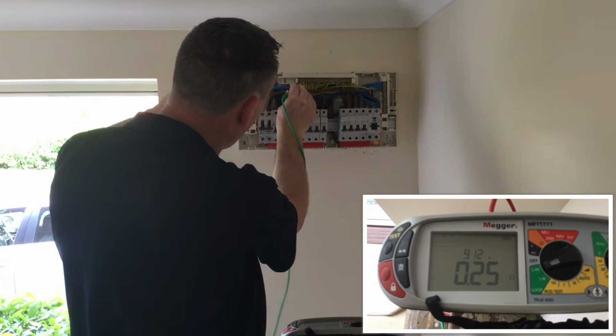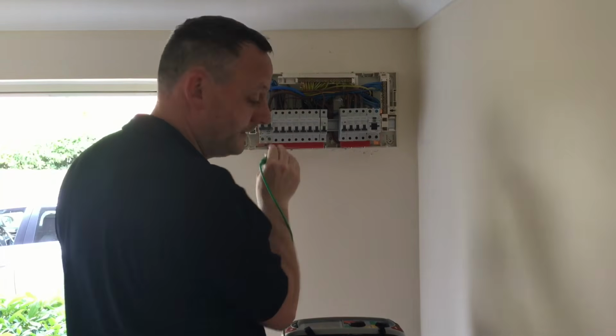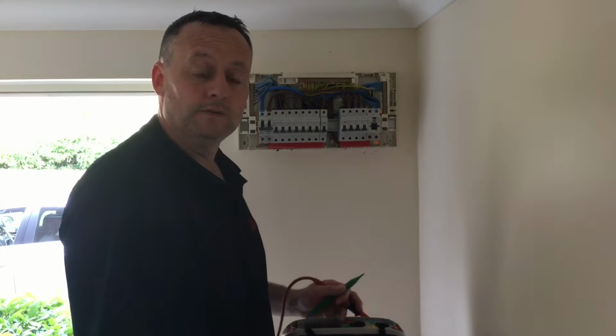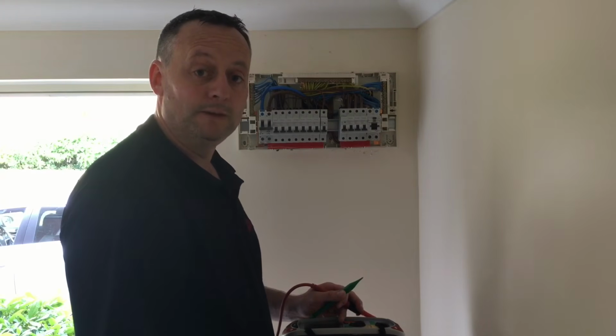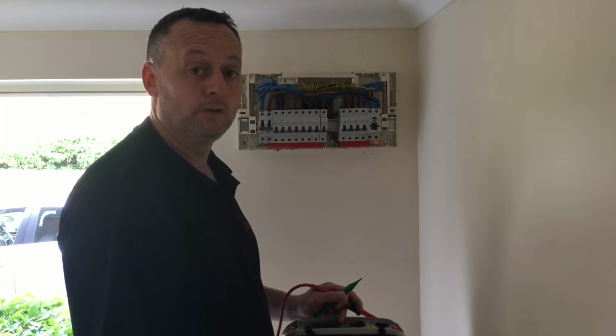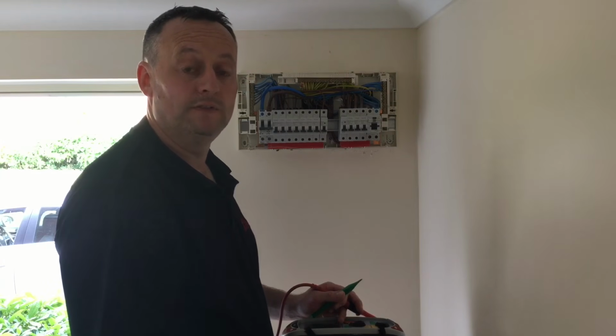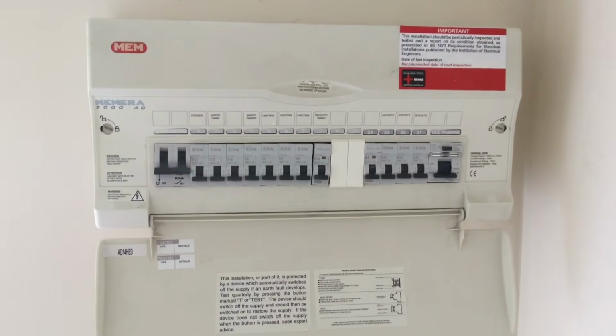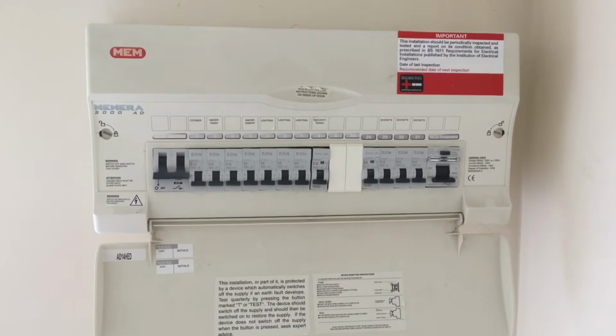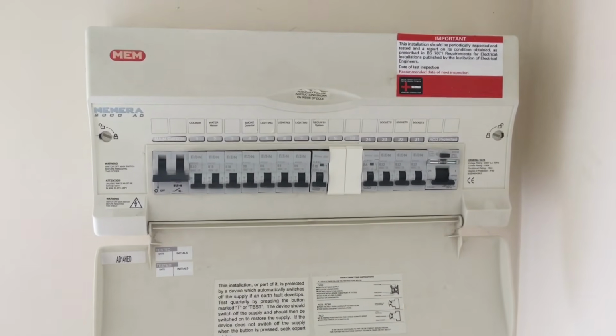I'm going to pull off the line conductor and I'm going to pull off the earthing conductor. There we go. The external earth fault loop impedance has been measured. It's less than the 0.35 ohm maximum, being 0.25. Therefore, we've proved the external earth fault loop impedance meets the requirements. With the earthing conductor reconnected and the distribution board cover replaced, we can now turn on the main switch and individual circuit breakers.